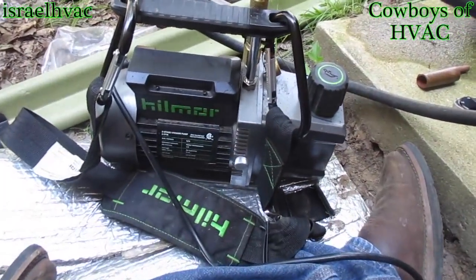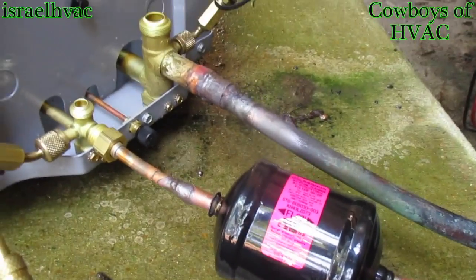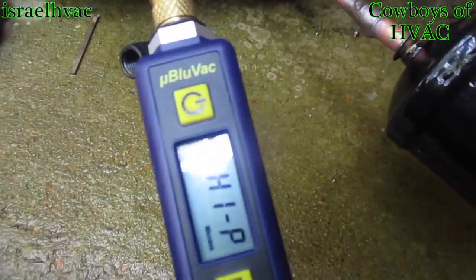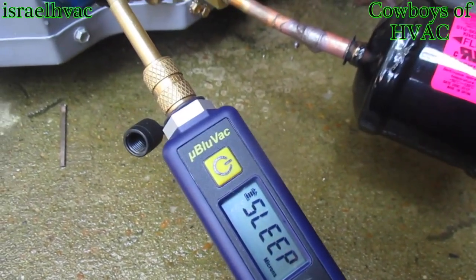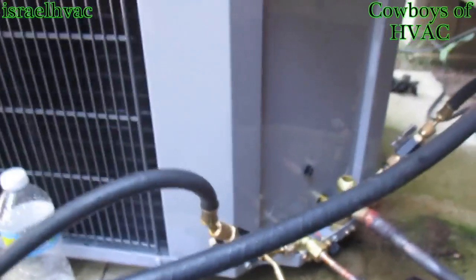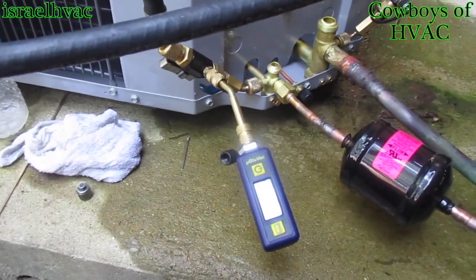Alright guys, I have the ICP in a vacuum. Everything's brazed up, we've got our dryer in. I have my new mini BluVac gauge. I'm going to open up here, and then open up over here. It's in sleep mode right now, but it'll come awake here in a minute. We'll start pulling some microns. I'm going to go inside and rewire the air handler and mount in my new thermostat and wire that up.